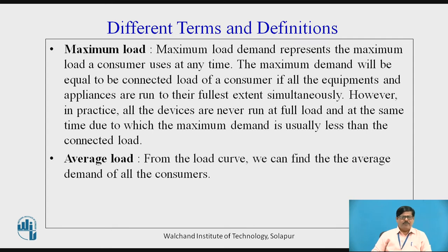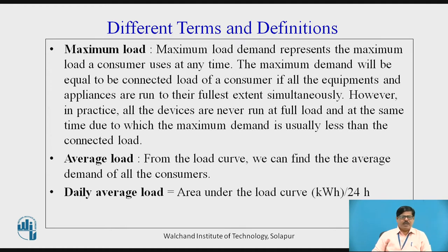Average load can be found from the load curve. For a daily load curve, the daily average load is calculated by taking the area under the load curve, expressed in kilowatt-hours, divided by the time duration of a day — that is 24 hours. This gives us the average load.